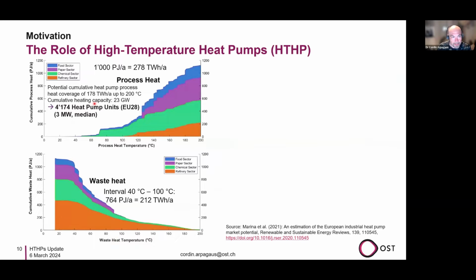There are also studies estimating the potential number of heat pumps, here a study estimating the European market across four sectors: food, paper, chemical, and refinery. This shows cumulative process heat and waste heat numbers, with process heat curves on top and waste heat curves below. The idea is to make use of waste heat at temperatures between 20, 40, 60, 80 degrees, and upgrade it to higher process heat temperatures above 80, 100, 120, up to 200 degrees.